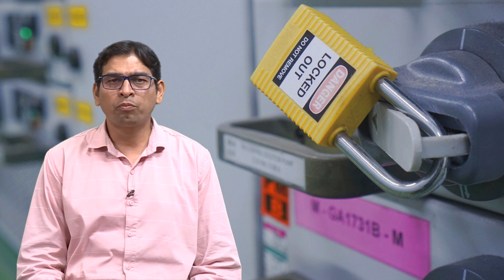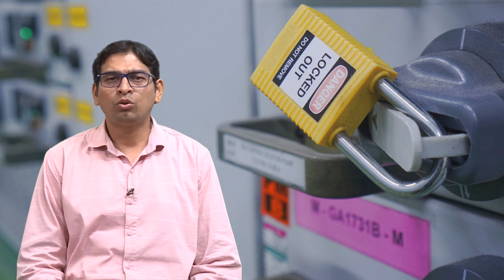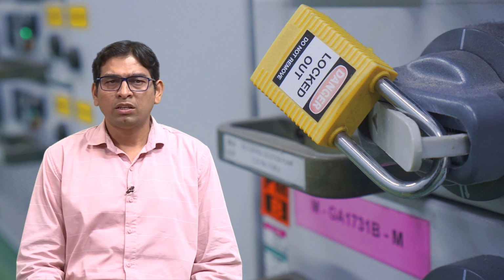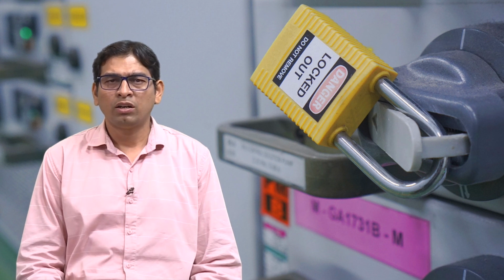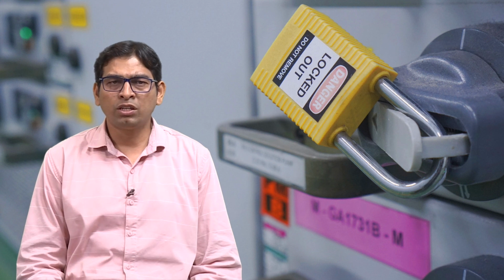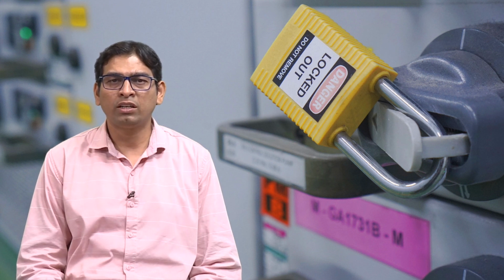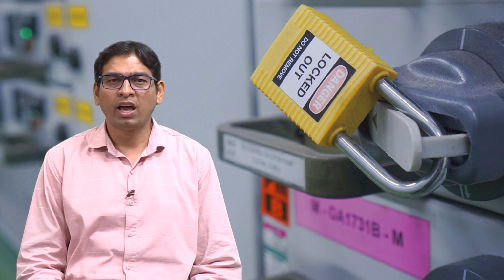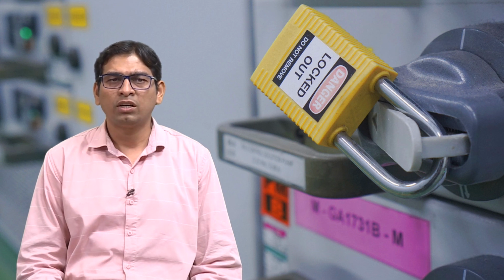Various types of equipment may require you to release spring tension or dissipate extreme hot and cold temperatures as well. After getting rid of any residual energy, you may still have to block off part of the machine that could move while you are working and install additional lockout tagout mechanisms to complete the lockout of the system.